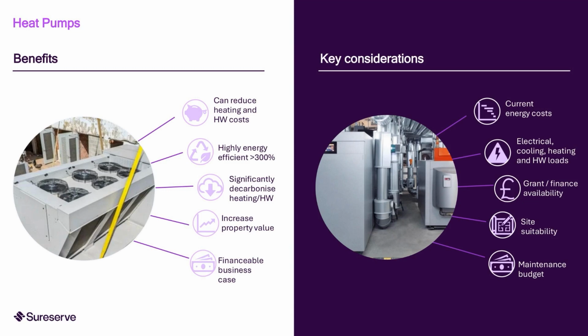The benefits of heat pumps is we can reduce your heating and hot water costs. High energy efficiency of greater than 300% can be utilised in certain circumstances. And what we want to see from a heat pump deployment is really maximising what we call the seasonal coefficient of performance, or you may hear it referred to as SCOP or just COP. And that is how many kilowatts of electricity do you need to get a set amount of kilowatts out of the heat pump. So typically we can operate this COP above 3, and we want to utilise a good flow temperature of around 65 degrees.